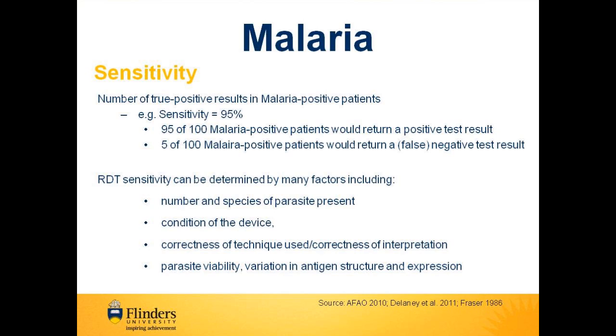Sensitivity is the number of true positive results in patients infected with malaria. For example, if the sensitivity of a device was 95% and we tested 100 malaria positive patients, 95 out of the 100 patients would give a positive result — the patient is truly positive for malaria infection — and the remaining 5 out of 100 results would be false negative results, meaning that the patient was infected with malaria, but the test came back negative. RDT sensitivity can be affected by many factors, such as the species of parasite, the number of parasites present or the parasite density, the condition of the device, the correctness of technique used by the operator, the parasite viability, and the variation in antigen structure and expression.